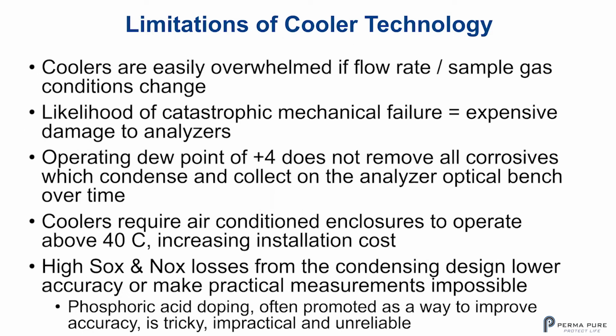So here are some specific limitations of cooler technology. Coolers are the technology that is most often used, primarily because of the low acquisition cost. But coolers are easily overwhelmed if the flow rate and sample gas conditions change. This is because they have a very narrow range of operation depending on how they're specified, and they really can't go over that too well. You also have a likelihood of catastrophic mechanical failure, which equals expensive damage to analyzers.